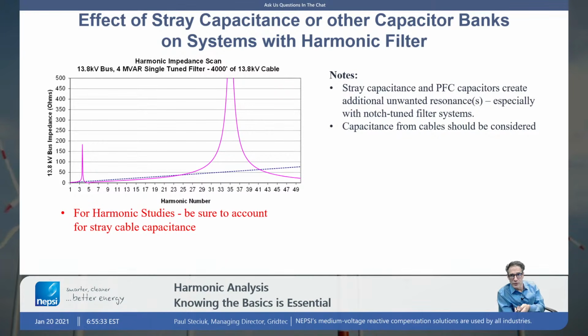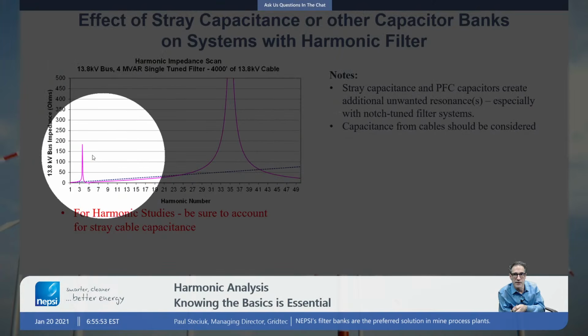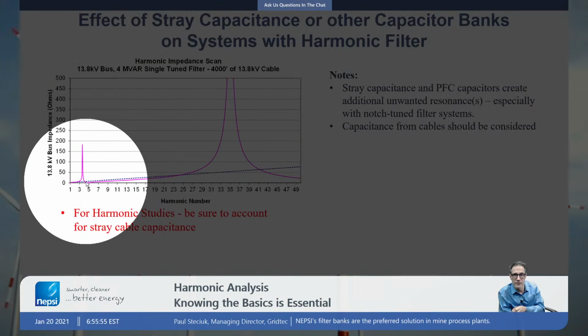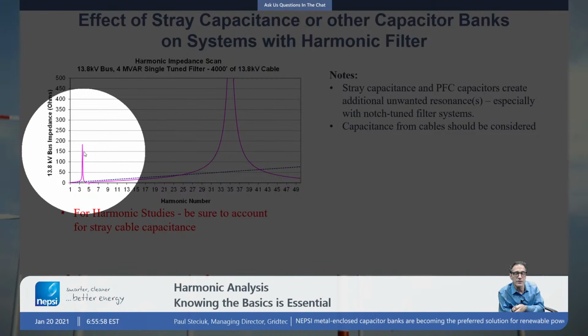Oftentimes we have a customer who will install a harmonic filter, and I'll say, well, I've installed my harmonic filter, so now I don't need to worry about capacitor banks or capacitance within a network, and it's just certainly not true. Whenever you have a capacitor in a network, I have a resonance. When I have a filter in a network, I still have a resonance. In this case, I have some cable capacitance here, and I have a filter here with this resonance. So there's two resonant points.